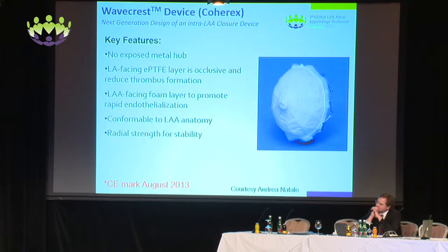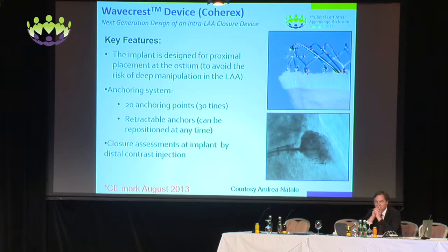As a new device, there's also the Wave Crest. The device has been CE marked since August 2013. Features of that device include no metal hub on the left atrial side. The membrane on the left atrial side is made with PTFE to be more occlusive and also to prevent thrombus formation. There's a foam layer on the LAA side to promote rapid endothelialization. The device is highly conformable to the left atrial appendage, but also has enough strength in theory to remain in place. The implant is designed for proximal implantation at the level of the ostium, so you don't want to go far in the appendage with the device.